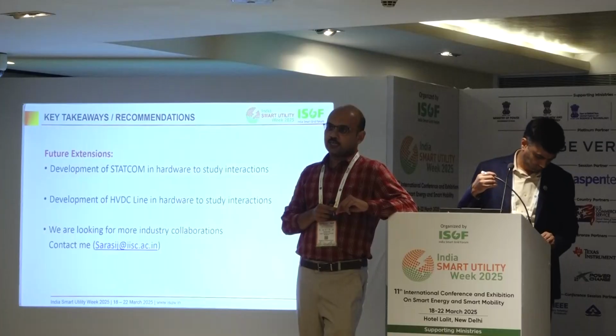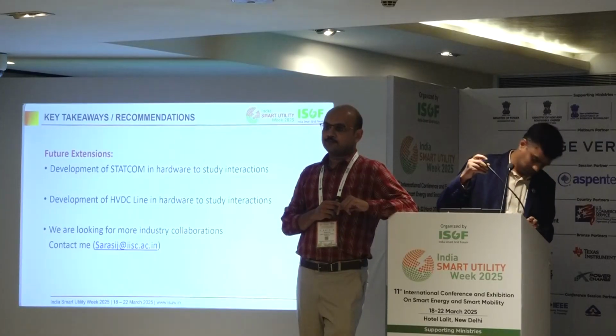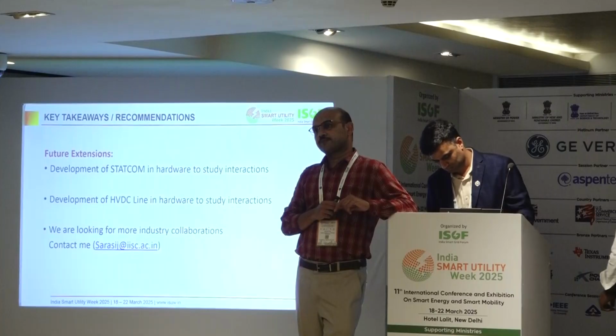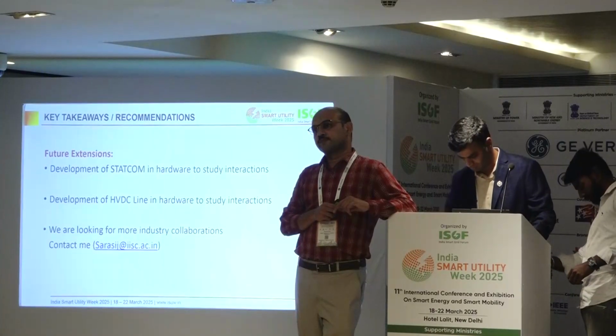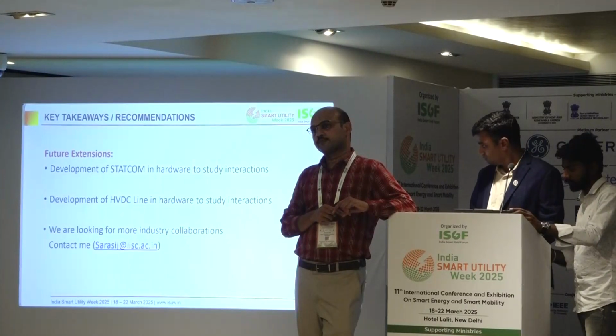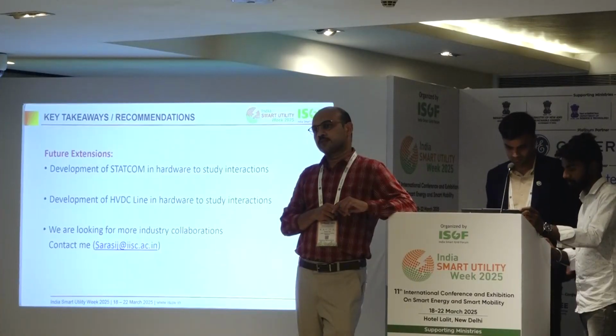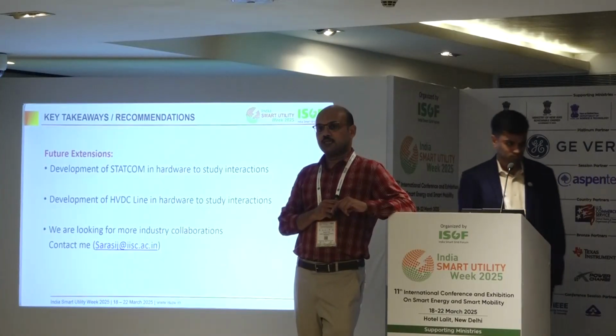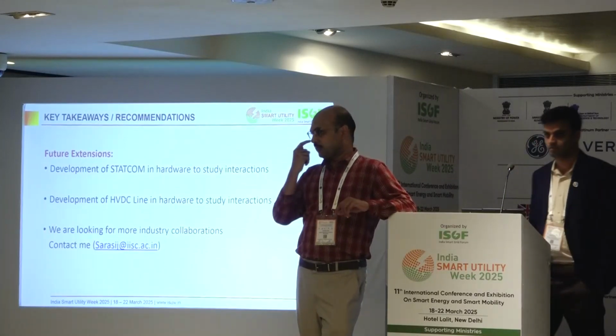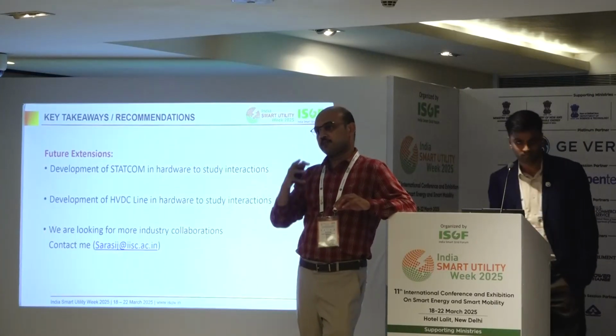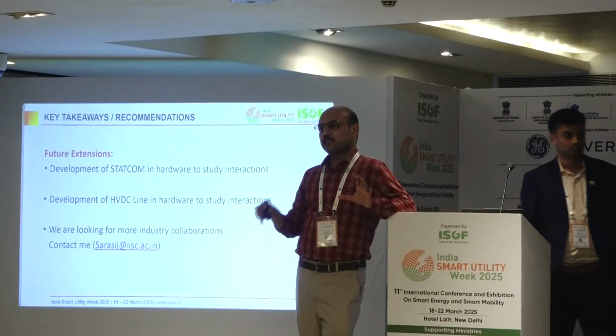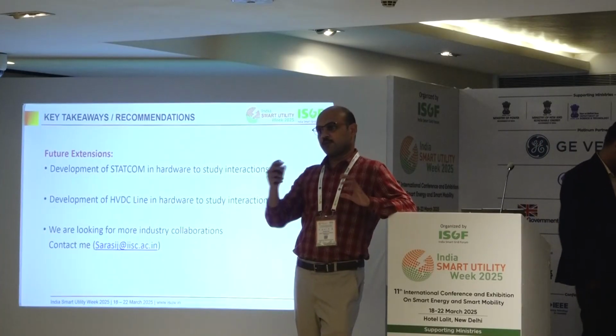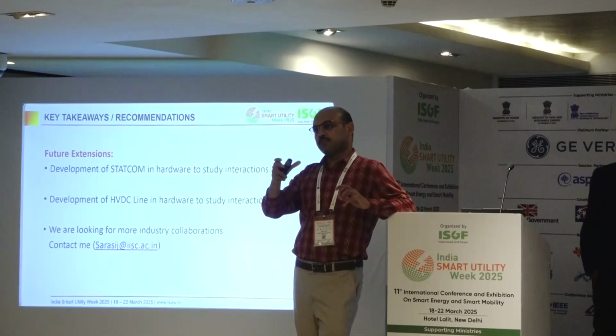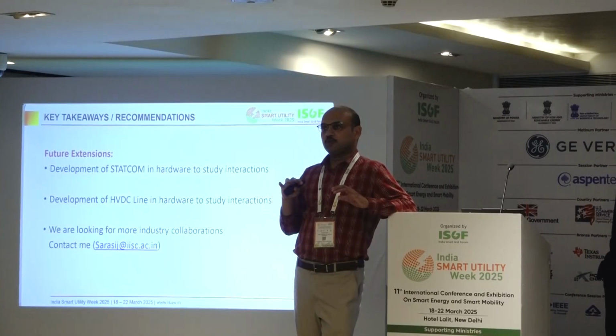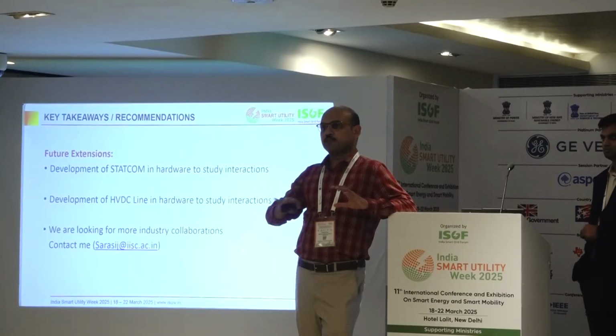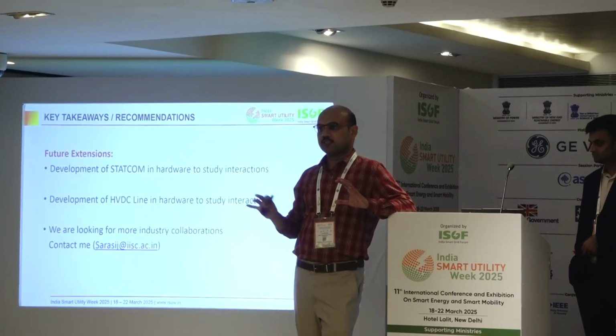For grid forming, did you basically just allow the volt-var controls a wider range, and also assume the hardware can support that amount of reactive power capability? Basically we had a limit and we implemented group control - based on the group it gives the set point, and there is a virtual impedance control for fault. When a fault happens, it introduces a virtual impedance so that the current is limited. So there is a limit on the current and everything - that's how it is designed.